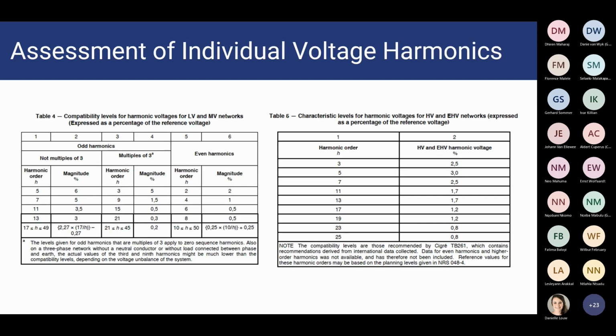Okay, then in the NRS 048, table 4 and table 6 define the limits, the compatibility levels, for individual voltage harmonics. Table 4 defines the levels for LV and MV networks, and table 6 for HV and extra high voltage networks. You can see that there are limits for your odd harmonics and also your even harmonics. At high voltage and extra high voltage, it's only for certain odd harmonics where limits are specified. And this is all as a percentage of your fundamental voltage.